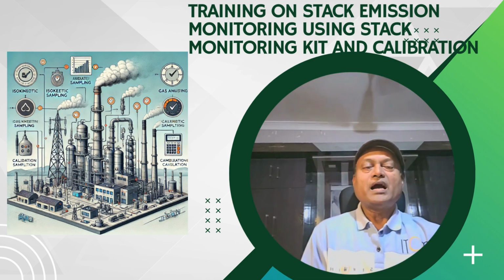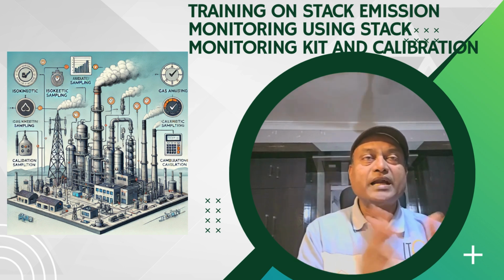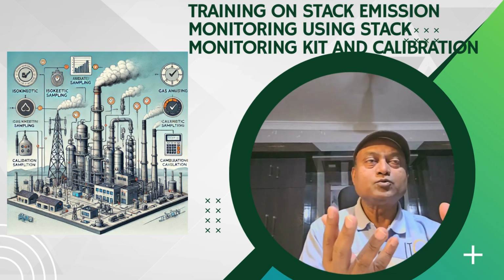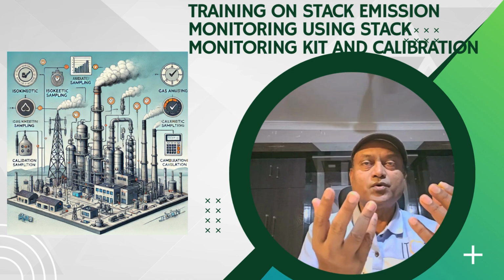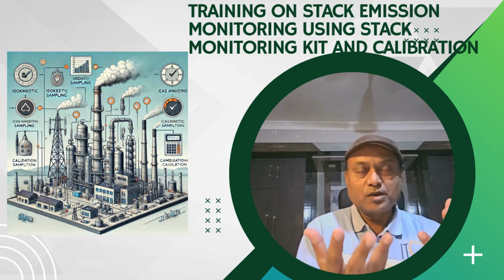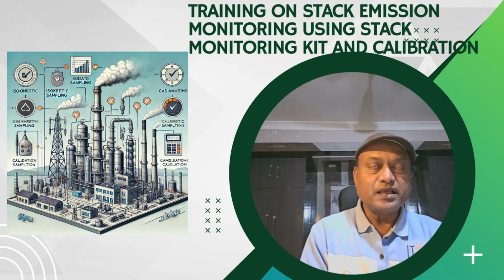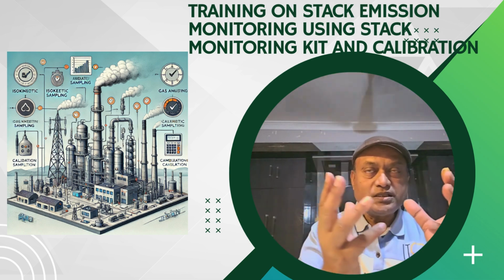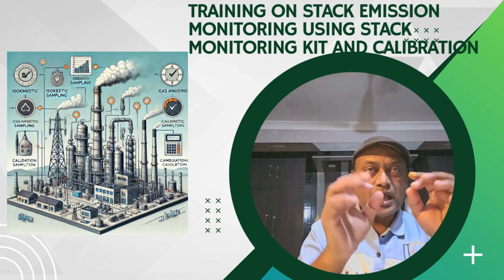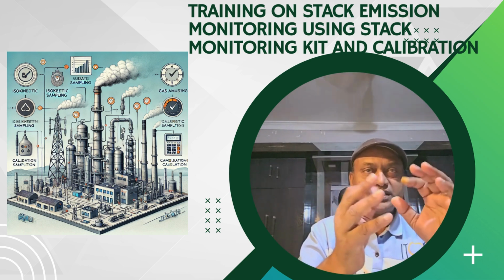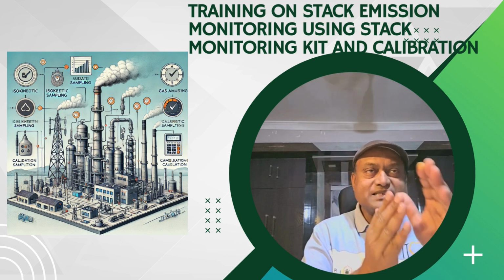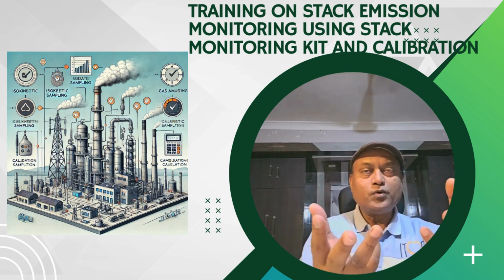Measurement techniques: isokinetic sampling. Ensure that the sampling rate of gas through the probe matches the flow rate of the stack, because you have to measure the flow rate of the stack.